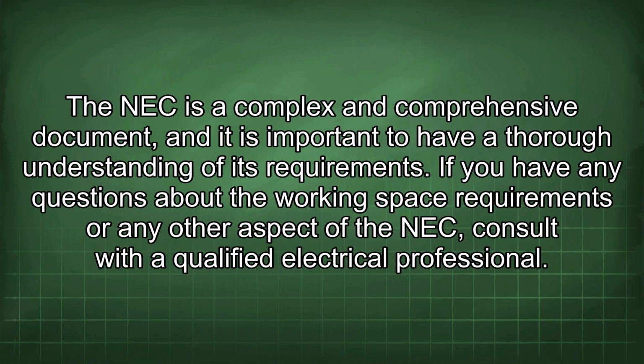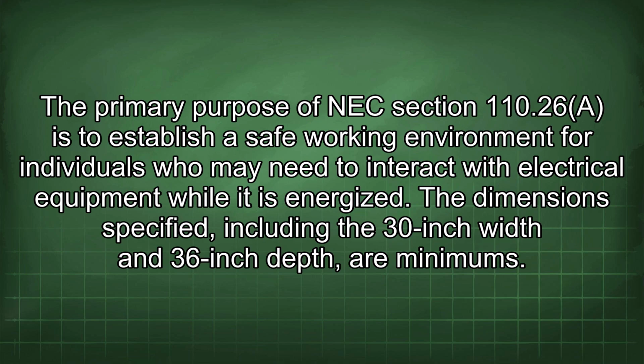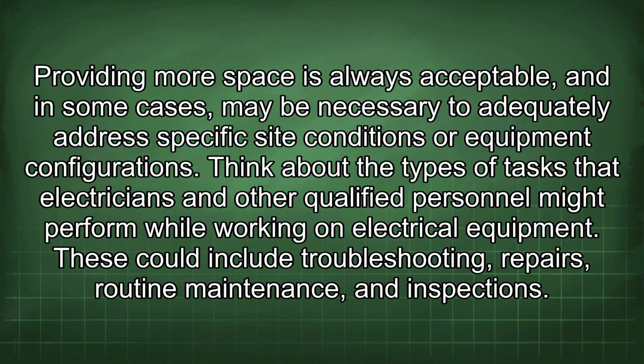The primary purpose of NEC Section 110.26 is to establish a safe working environment for individuals who may need to interact with electrical equipment while it is energized. The dimensions specified, including the 30-inch width and 36-inch depth, are minimums. Providing more space is always acceptable and in some cases may be necessary to adequately address specific site conditions or equipment configurations.